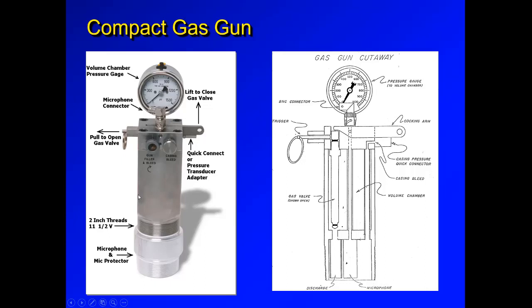We have an 8 cubic inch, I think it's a 7 or 8 cubic inch chamber where we can compress gas and do explosion shots, or we can let the pressure come from the well into the chamber to do implosion shots. There is a gas valve, and there's an O-ring down here, a cylinder chamber, and that will be a common part for replacement when you're doing gun maintenance.